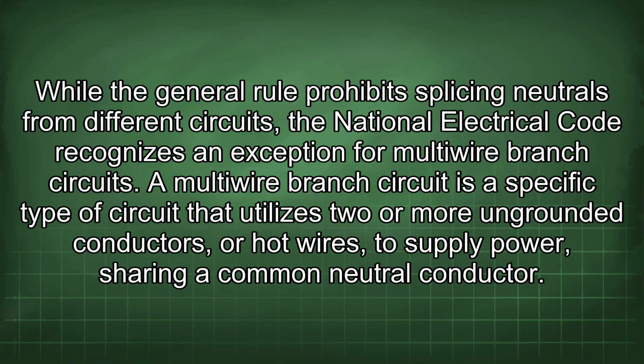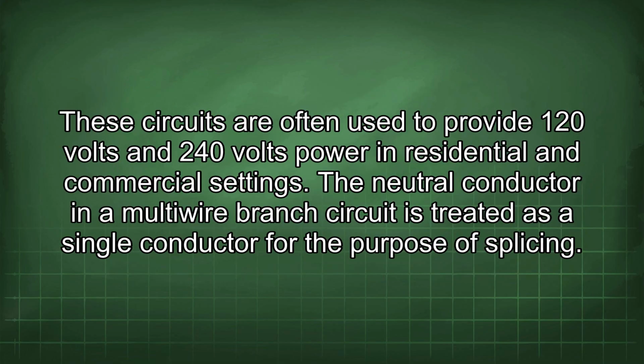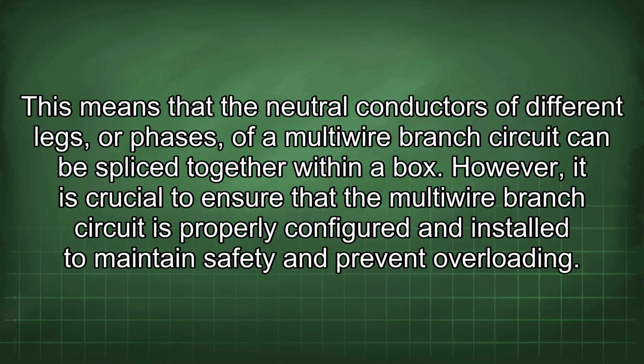While the general rule prohibits splicing neutrals from different circuits, the National Electrical Code recognizes an exception for multiwire branch circuits. A multiwire branch circuit is a specific type of circuit that utilizes two or more ungrounded conductors, or hot wires, to supply power, sharing a common neutral conductor. These circuits are often used to provide 120 volts and 240 volts power in residential and commercial settings. The neutral conductor in a multiwire branch circuit is treated as a single conductor for the purpose of splicing. This means that the neutral conductors of different legs, or phases, of a multiwire branch circuit can be spliced together within a box. However, it is crucial to ensure that the multiwire branch circuit is properly configured and installed to maintain safety and prevent overloading.